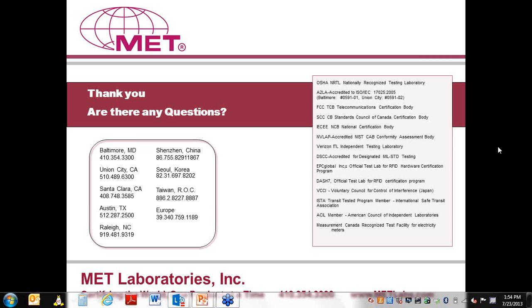And then the only other thing I could add to that is, besides there being a UL 61010 third edition standard, there may in fact also be a separate document that just covers the national differences, basically those requirements that are different from the IEC version of the standard. Sometimes there's one or both of those documents available. As far as how this is addressed at MET, if the standard has a different requirement, we're going to require each requirement or the more stringent of the two. It's just as basic as that.